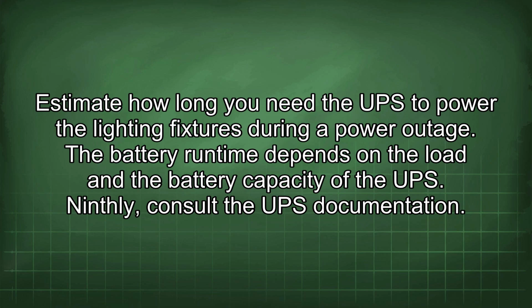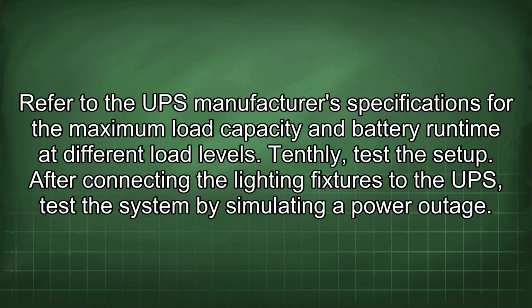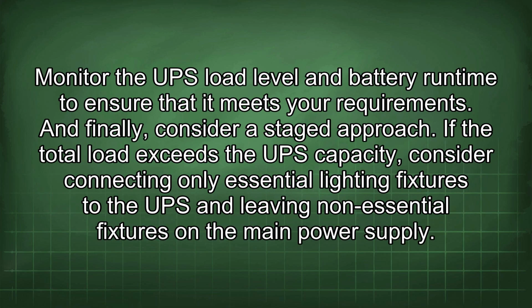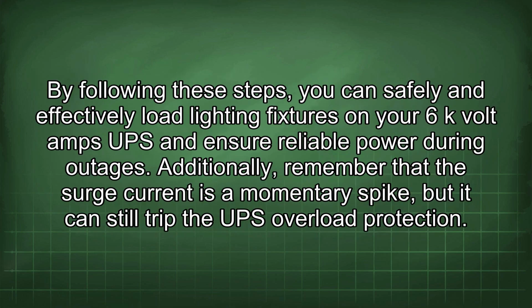Ninthly, consult the UPS documentation. Refer to the UPS manufacturer's specifications for the maximum load capacity and battery runtime at different load levels. Tenthly, test the setup. After connecting the lighting fixtures to the UPS, test the system by simulating a power outage. Monitor the UPS load level and battery runtime to ensure that it meets your requirements. And finally, consider a staged approach. If the total load exceeds the UPS capacity, consider connecting only essential lighting fixtures to the UPS and leaving non-essential fixtures on the main power supply. By following these steps, you can safely and effectively load lighting fixtures on your 6 kVA UPS and ensure reliable power during outages.